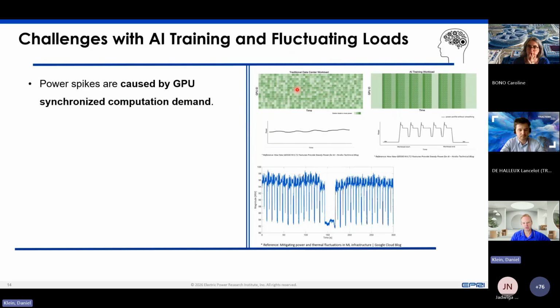When you have a data center that typically provides cloud service, the fluctuation of energy demand is fairly flat, typically between 10 to 15% over the time of the day. A lot is caused by when people come to the office and also the outside temperature that drives the cooling need. What you see here, that green mosaic, is the GPU cluster and racks and when they perform workloads, so you see more of a harmonic distribution, and that reflects in that flat power curve.